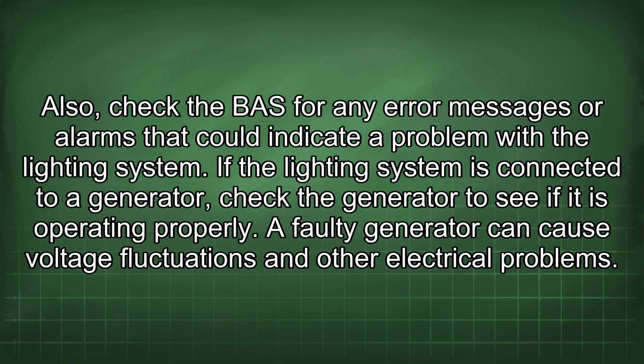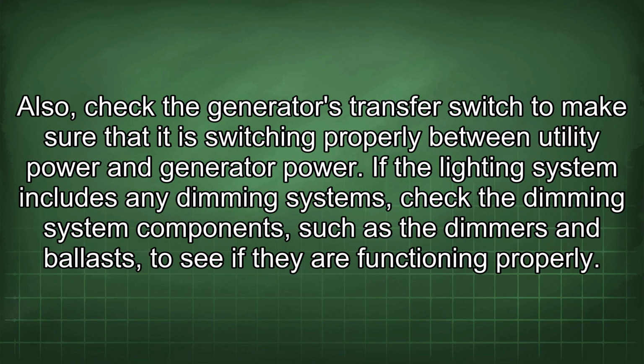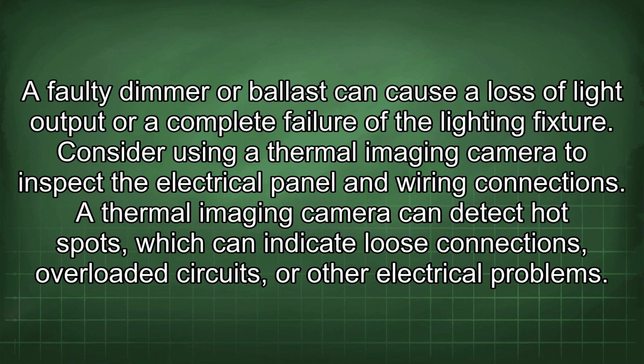If the lighting system is connected to a generator, check the generator to see if it is operating properly. A faulty generator can cause voltage fluctuations and other electrical problems. Also, check the generator's transfer switch to make sure that it is switching properly between utility power and generator power. If the lighting system includes any dimming systems, check the dimming system components, such as the dimmers and ballasts, to see if they are functioning properly. A faulty dimmer or ballast can cause a loss of light output or a complete failure of the lighting fixture.